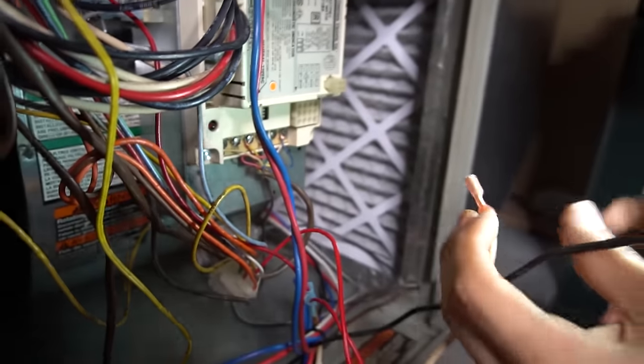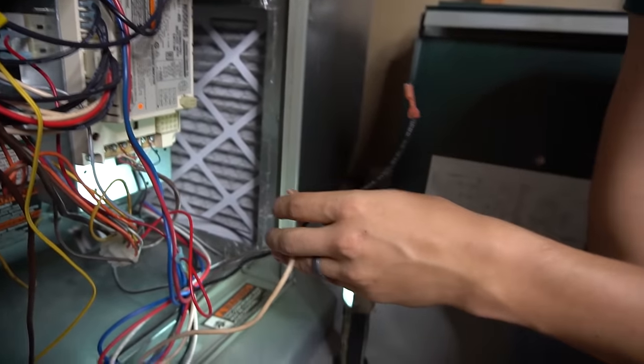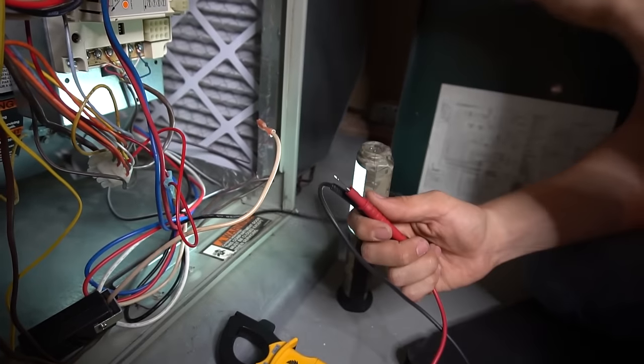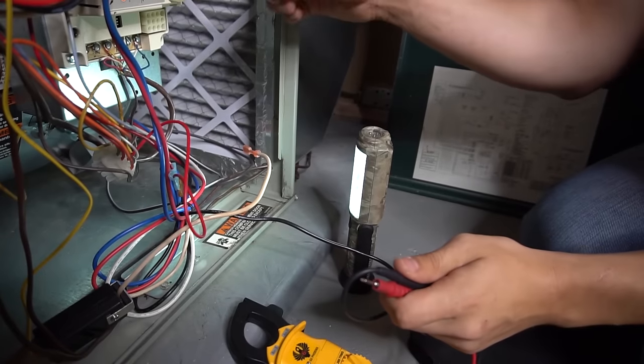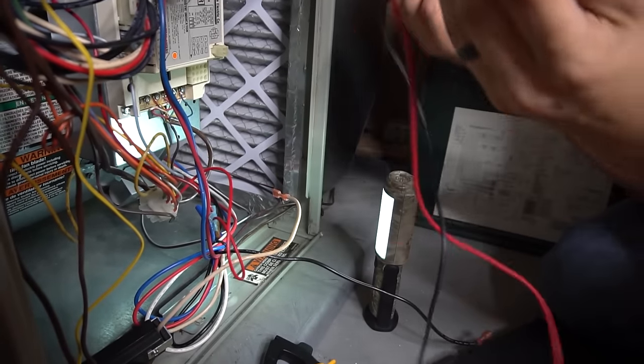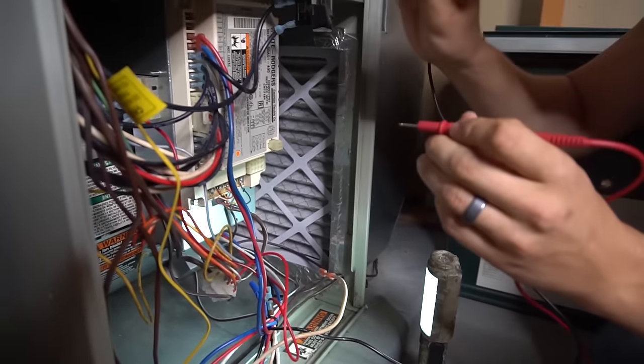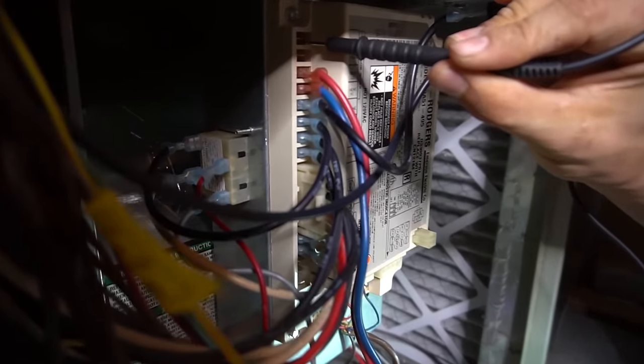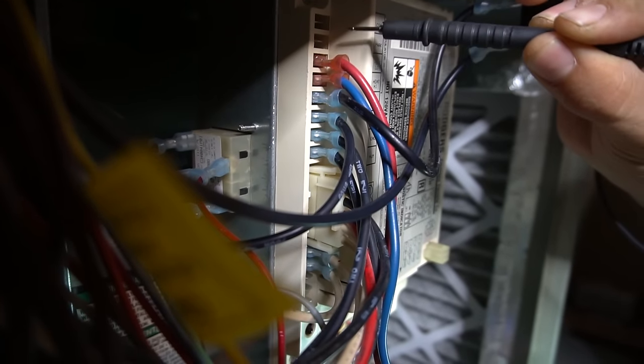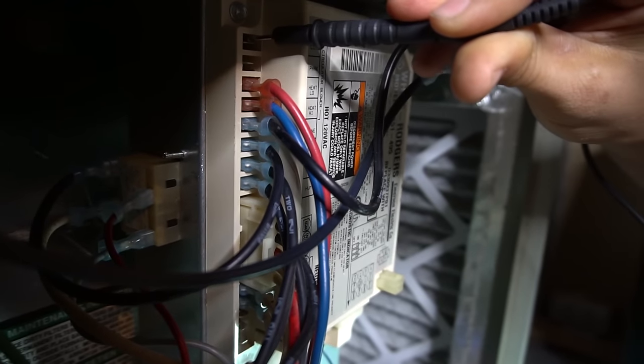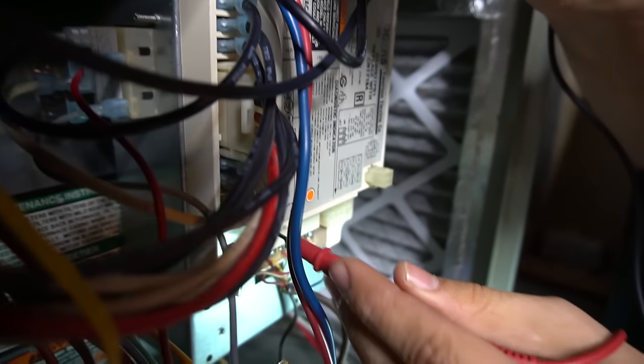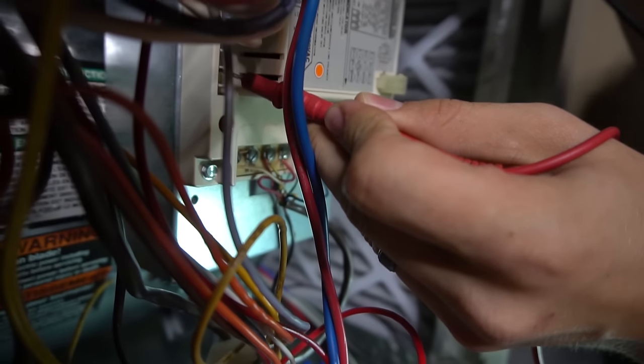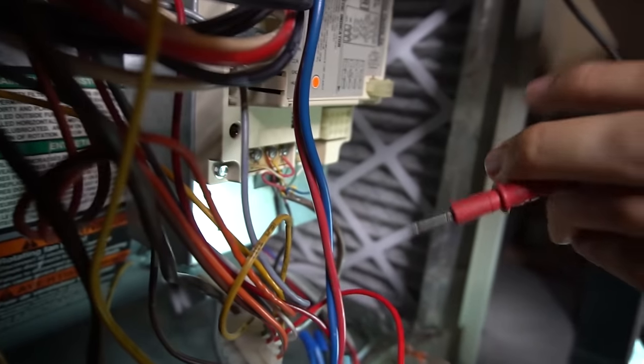After you have those two wires pulled off, with your thermostat calling for cooling, your outside unit running, the fan should be turning on. So what you want to do is just verify that it's getting power. So you'll put one lead on the cool spade where you pulled the cooling speed wire off of. One of your leads will go on that and the other one will go on the common or the circulator common, the other wire that you pulled off. You want to have that set to voltage.